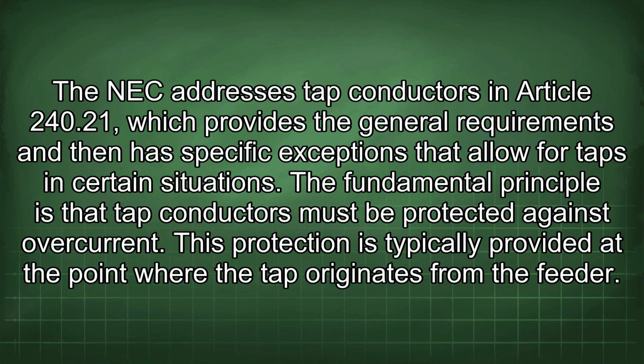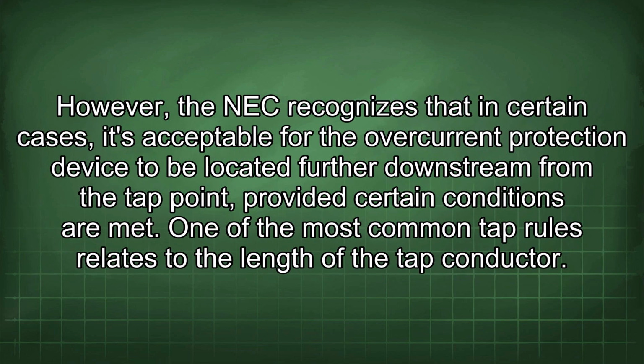The NEC addresses tap conductors in Article 240.21, which provides the general requirements and then has specific exceptions that allow for taps in certain situations. The fundamental principle is that tap conductors must be protected against overcurrent. This protection is typically provided at the point where the tap originates from the feeder. However, the NEC recognizes that in certain cases, it's acceptable for the overcurrent protection device to be located further downstream from the tap point, provided certain conditions are met.